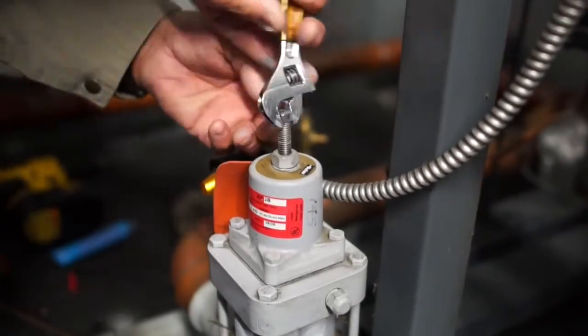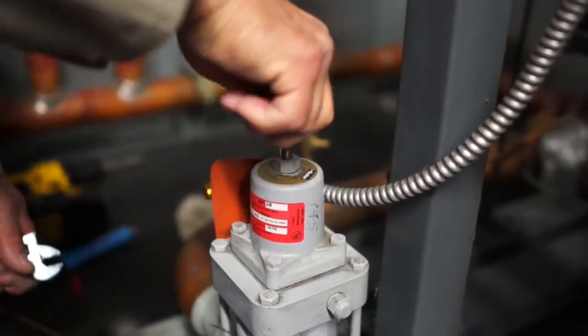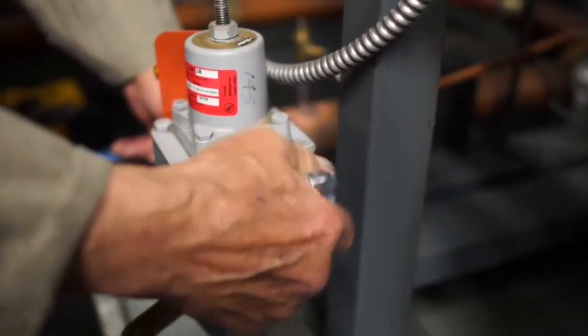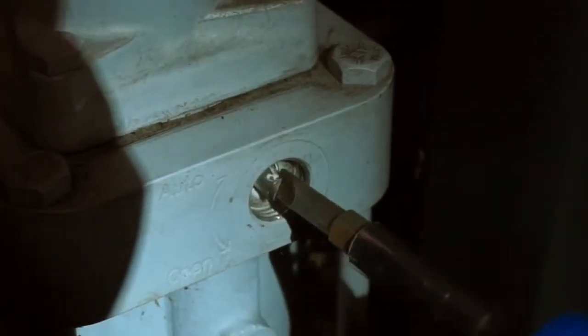First, back out the adjustment screw on top of the bonnet on the existing valve until it can be loosened by hand. On the side of the existing adapter, remove the cap and turn the manual open feature to the open position.